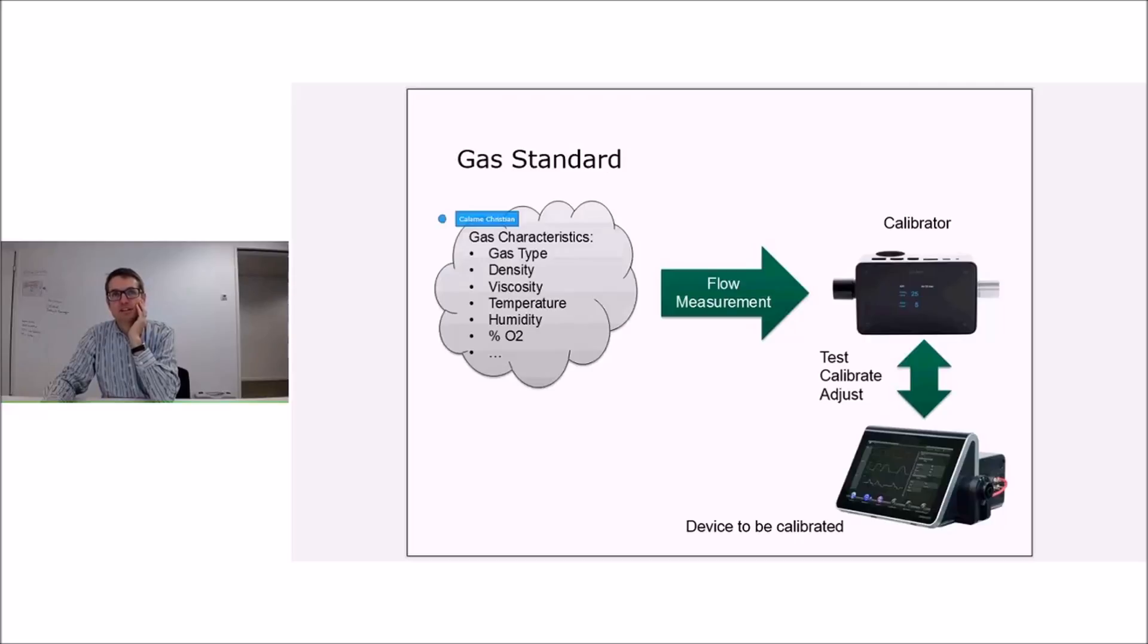The gas characteristics which we are about to measure—that's the gas we're actually measuring—has certain properties, and these properties have to be measured or dialed in in order to be compensated. So basically for the measurement you don't need the gas standard. The gas standard only tells you how the measurements are displayed, because from these gas characteristics, let's say we're measuring a very hot gas or a very humid gas, when it's measured it's calculated into standard liters or standard liters per second or into standard conditions.